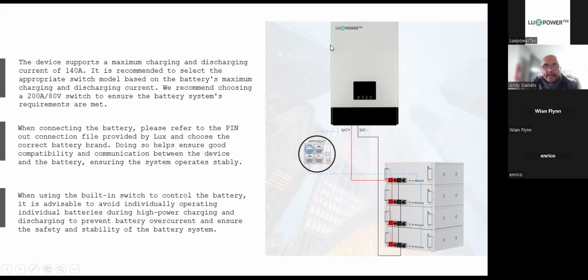All right. And then in this diagram here, we've obviously omitted the fuses and the switch, but we've discussed that in the previous diagram. Okay, so the device supports a maximum charging and discharging current of 140 amps. So you're going to have to put a minimum of 35 mil cable in for your DC, and it's recommended to select the appropriate switch model based on the battery's maximum charging and discharge current. So we recommend choosing a circuit breaker that is rated, obviously 140 amps is going to be the minimum entry requirement for your breaker or your fuse. But if you go for a 200 amp breaker, it far exceeds the system's capacity for one inverter. And obviously, it gives you peace of mind, as well as your customer or your end user.